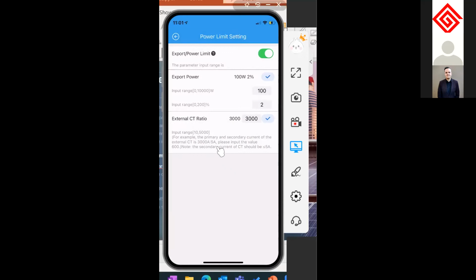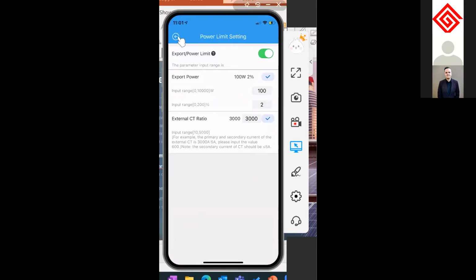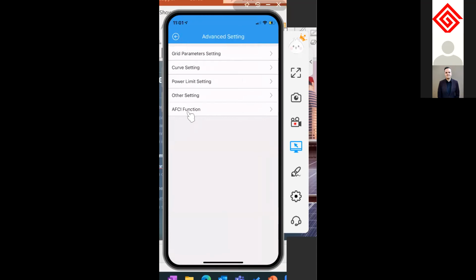So for the smart meters that are provided by GoodWe, so the one we saw before, those smart meters are supplied with special CTs that have 40 milliamps on the secondary side and 120 amps on the primary side. And if you divide 120 over 40 milliamps, then you will get 3000. So this is already set. And sorry, my phone locked. So when that's done, you just go back. And then here is also a function for AFCI functions and some other settings. But that is not really necessary.